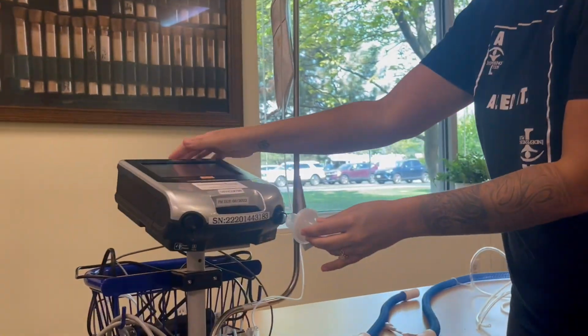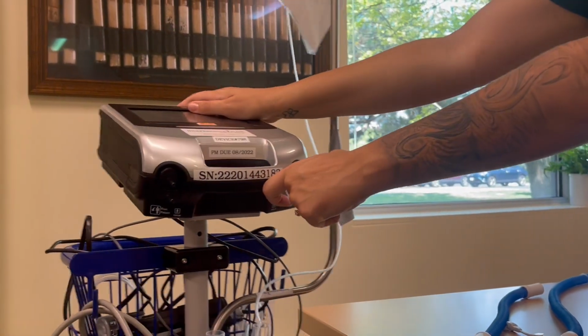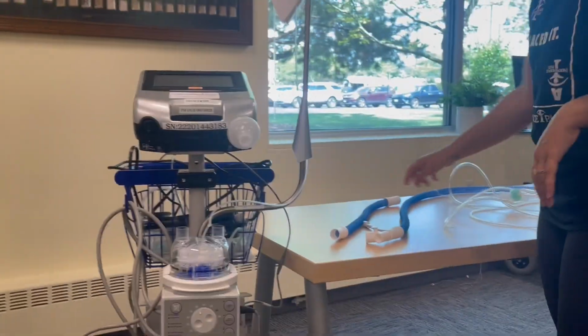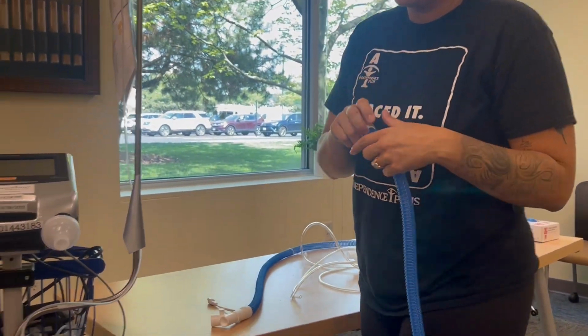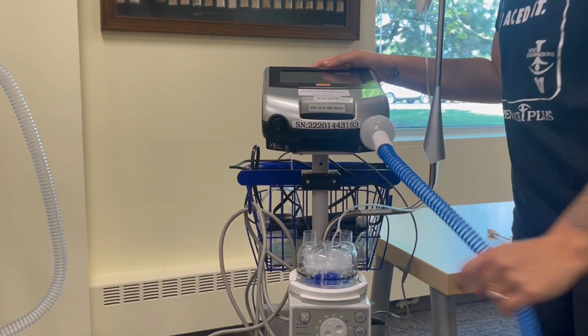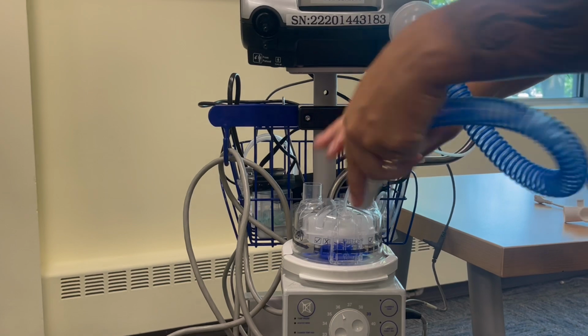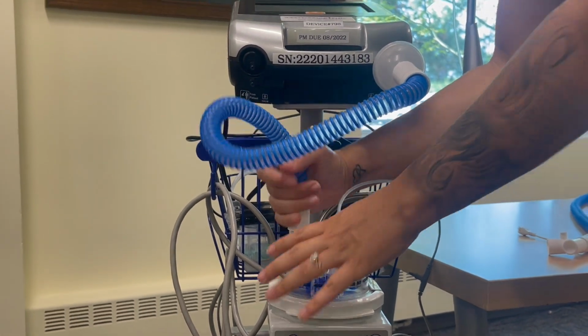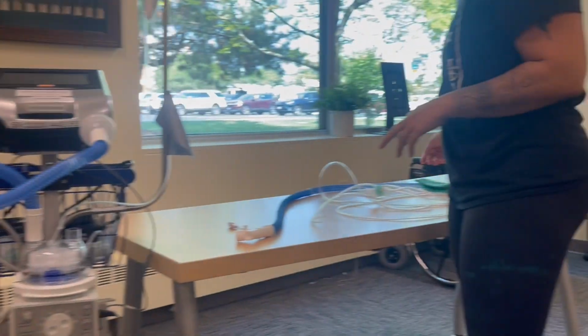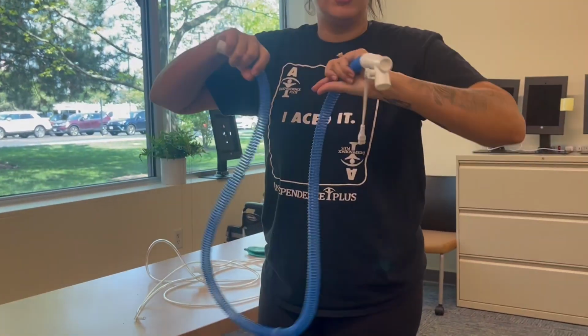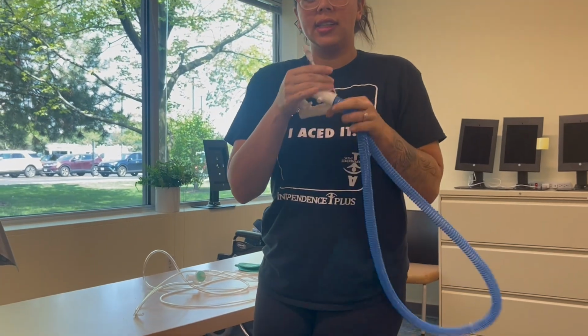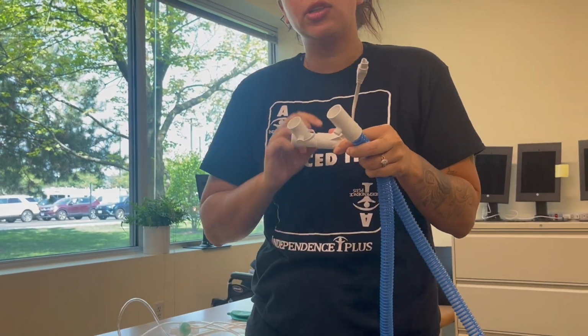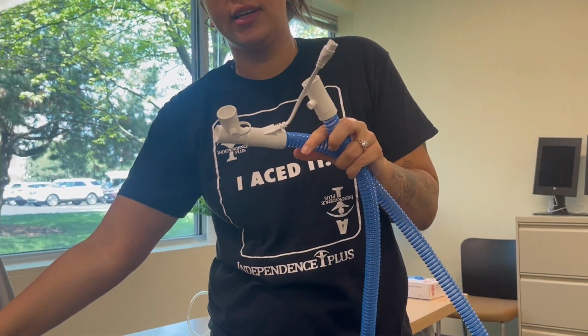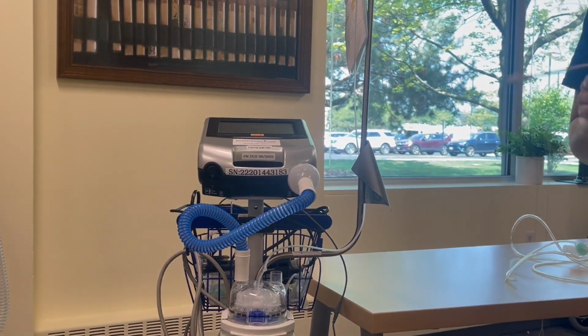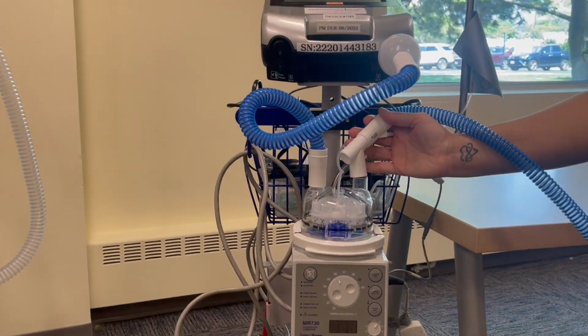So starting off with my bacteria filter, this is gonna plug into the ventilator. So that's gonna go right here. Turn this there. That's gonna go here. The next thing I'm gonna do is take my short tubing and plug this into the bacteria filter. And then it's gonna go into the MR730. Doesn't really matter what side you put it on. The next thing I'm gonna do is take my long tubing, and the long tubing actually has a part that's gonna plug into that adapter that I already plugged in. So I'm gonna make sure this part is on the heated humidity chamber so that it can plug into the adapter. So this is gonna plug in here.